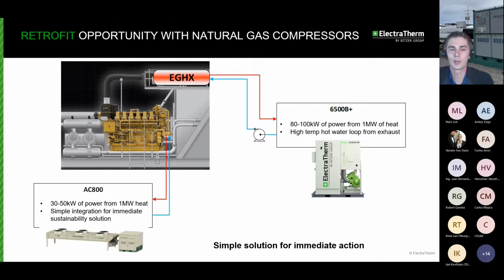Your typical power generation equipment can only operate at about 50% rated output. Below that, for extended periods of time, it typically doesn't function quite like designed. Our equipment has no issue with that since we're utilizing that Bitzer expander. It's more than capable of operating through a full range of inputs from the heat source. So if you have, again, engines that operate at variable loads or full out, doesn't matter, our units are going to operate continuously within that time.